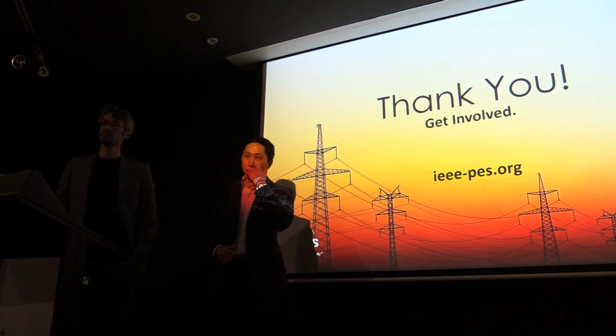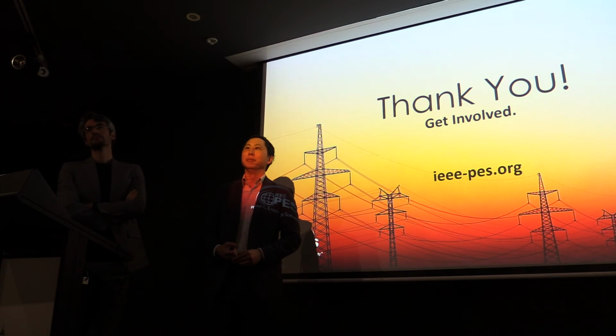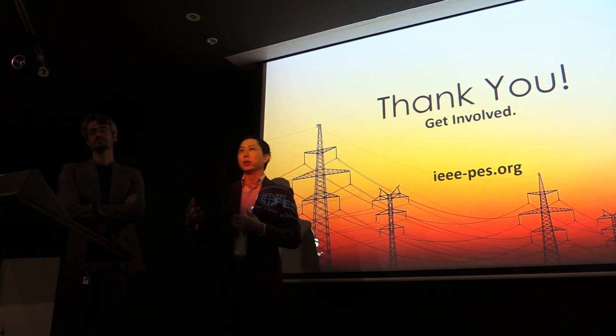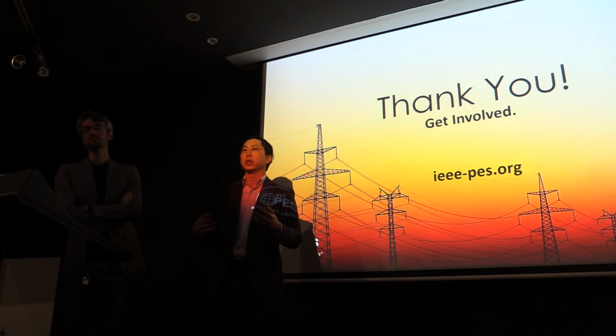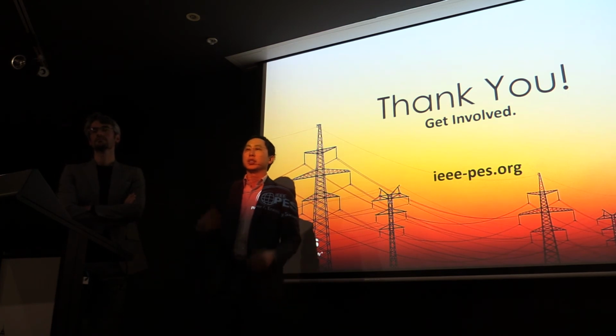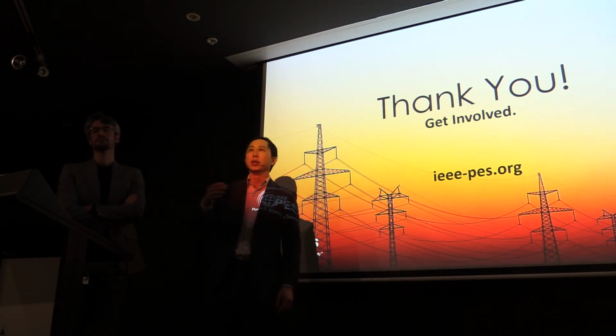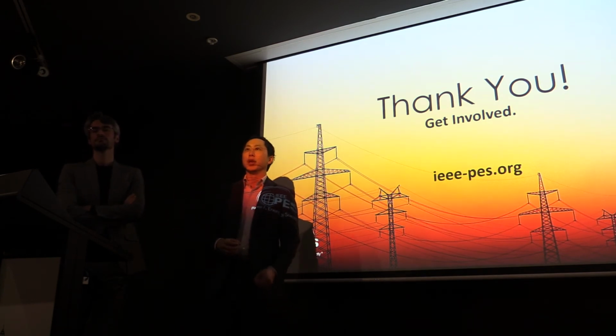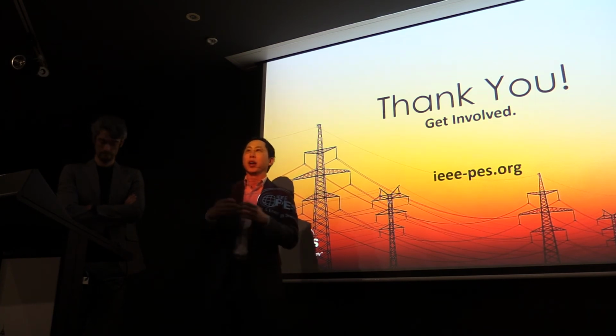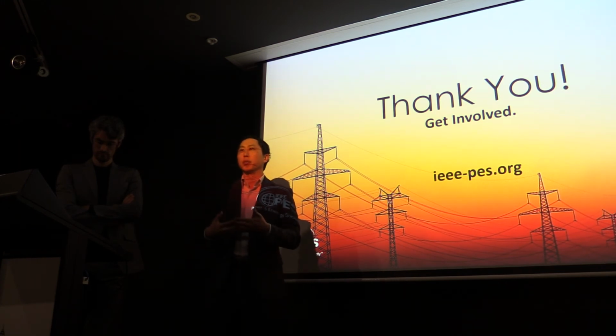Now, another thing: you didn't mention over-frequency response, load rejections that could occur. Does your tool take that into consideration? It can, but it's not a real material problem for us, because through the generator performance standards, all wind farms and other generators have to droop down on an over-frequency. If a generator is running above minimum generation, you've actually got headroom down. It's the other way around that's more of an issue, on the under-frequency side, because you might have all the generators running at maximum, and so you don't have any headroom up. Right, so that's what you need to provision for. But generally speaking, we don't have a problem with over-frequency response. We've actually never had a frequency deviation above 50.5 hertz.